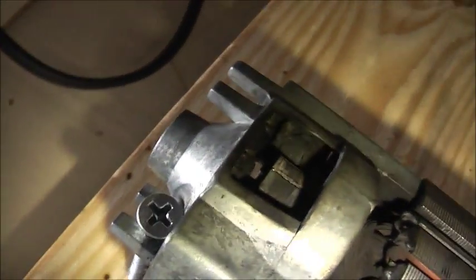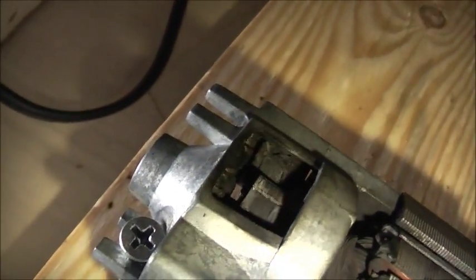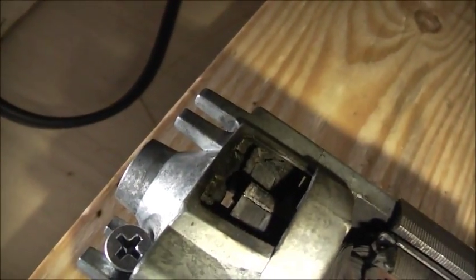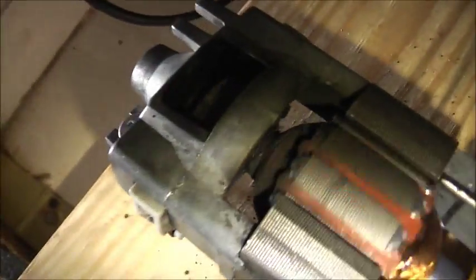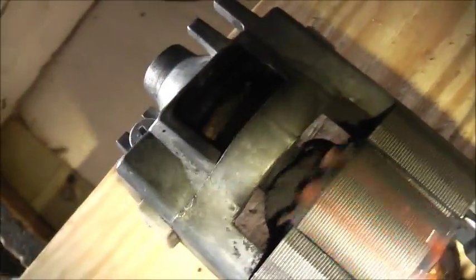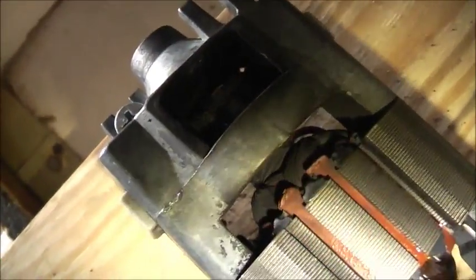Well, have a closer look at this motor. You can see that brush is on an angle there. It's only just touching the commutator. That's why I had that dead spot. There's a dead spot there.